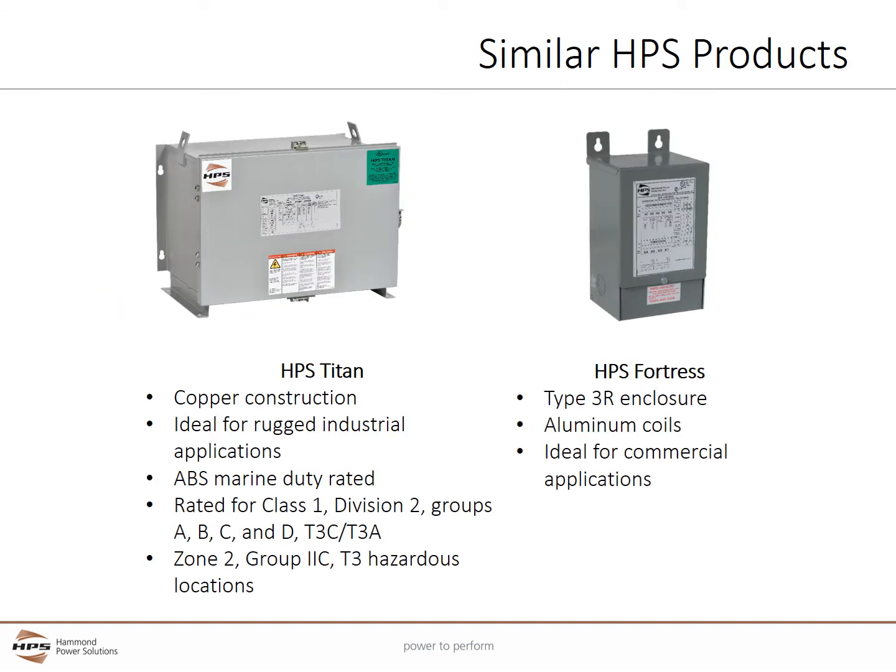HPS offers two other encapsulated transformer series. The HPS Titan series is suitable for industrial, hazardous, and marine duty locations. Its rugged design is suitable for hazardous class 1, div 2, and zone 2 locations. It is certified by the American Bureau of Shipping (ABS) for marine applications. All units are built with copper coils. Single phase uses type 3R construction, and three phase comes standard as type 4 enclosures. The HPS Fortress series is suitable for commercial and industrial applications where hazardous location or marine duty ratings are not required. Fortress uses type 3R enclosures and aluminum coils.